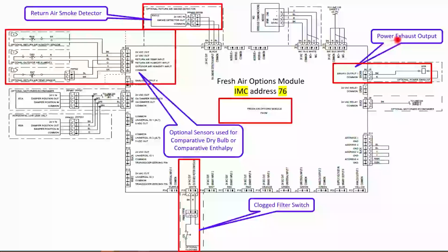Power exhaust, we see this a lot, and you're going to land that on your P6, and you're just going to tie it into a 24 volt. So that's just going into a relay that's going to supply your 24 volt to the power exhaust relay. And then you're going to set it up for power exhaust. And here's your clogged filter switch if you have that.